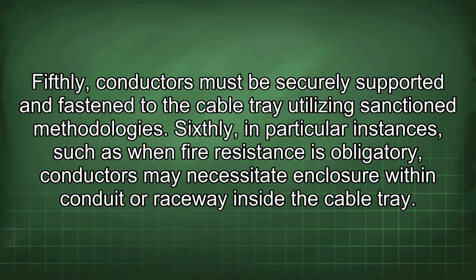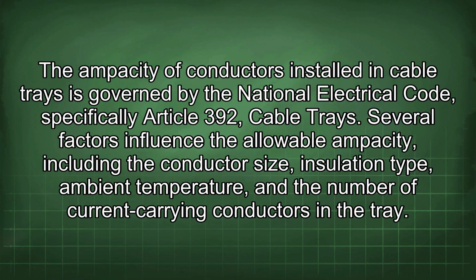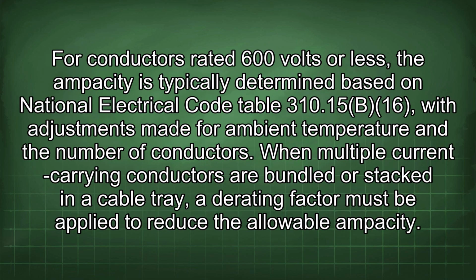the cable tray. The ampacity of conductors installed in cable trays is governed by the National Electrical Code, specifically Article 392, cable trays. Several factors influence the allowable ampacity, including the conductor size, insulation type, ambient temperature, and the number of current-carrying conductors in the tray. For conductors rated 600 volts or less, the ampacity is typically determined based on National Electrical Code Table 310.15(B)(16), with adjustments made for ambient temperature and the number of conductors.